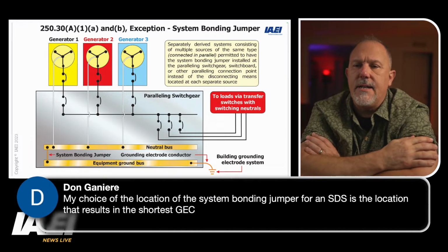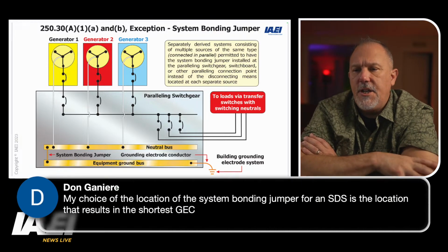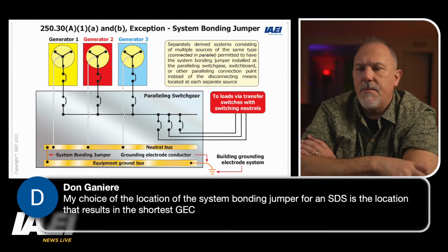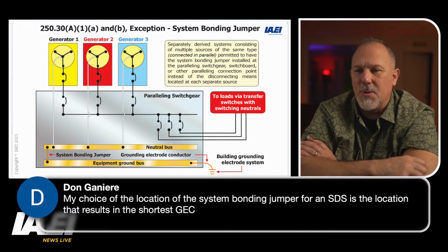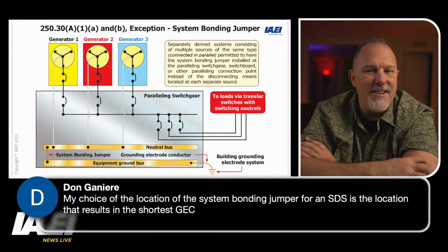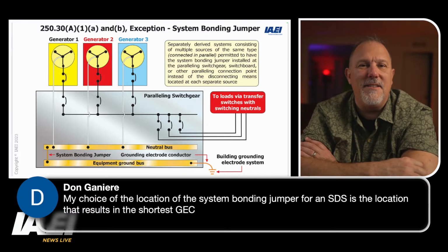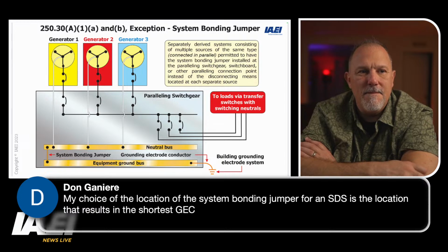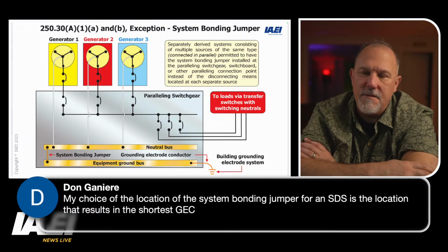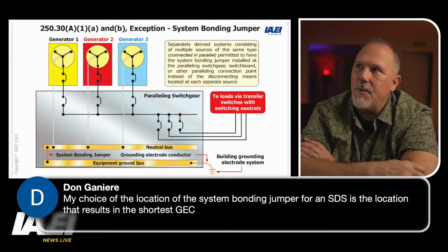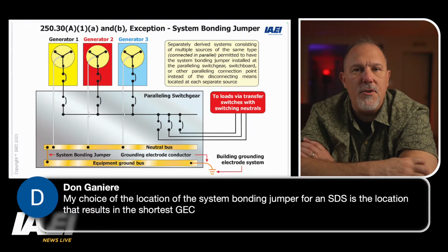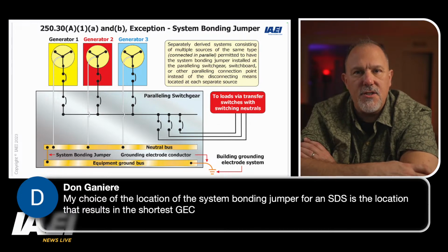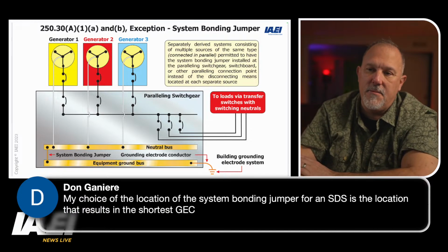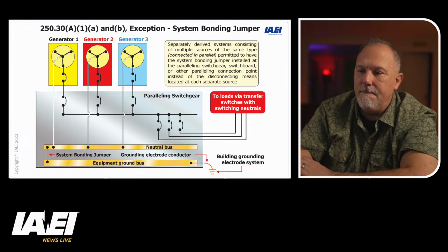Dawn says, my choice of the location of the system bonding jumper for a separately derived system is the location that results in the shortest grounding electrode conductor. You know, that's a very good perspective, Dawn. That's a very good perspective. And your grounding electrode conductor, which is going to be used to bond to your grounding electrode, and whatever gets you there in the shortest distance, that saves you the most money. I like it.